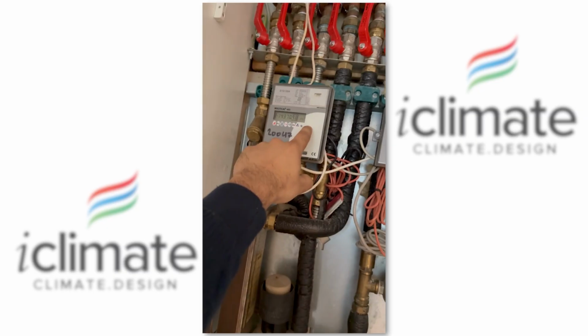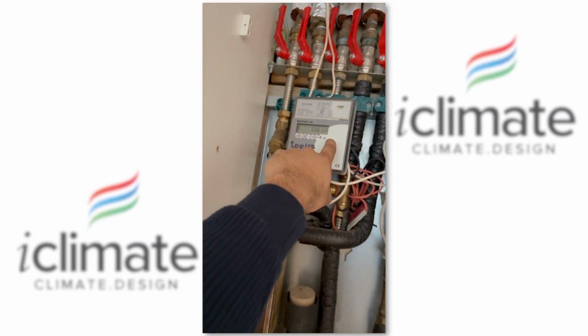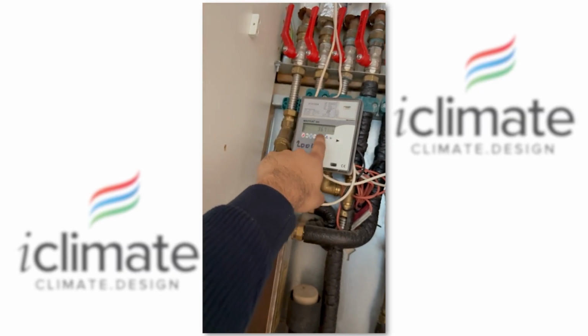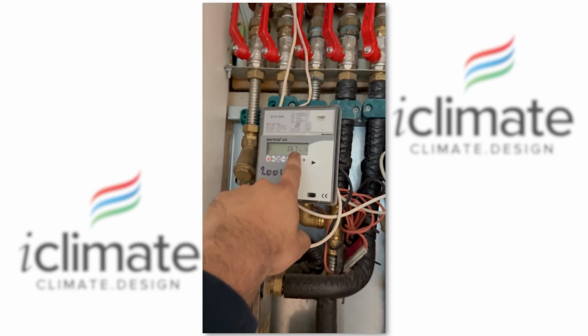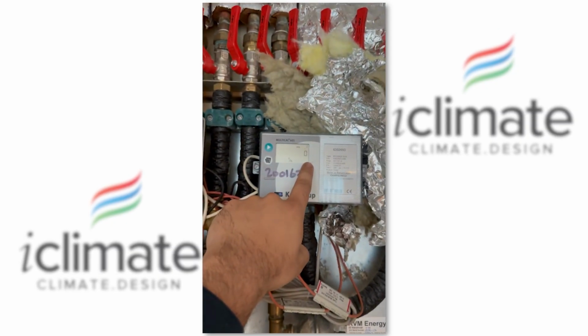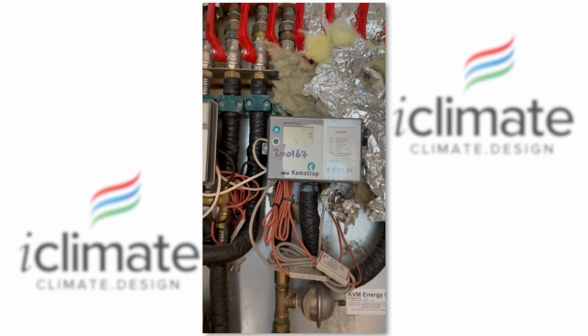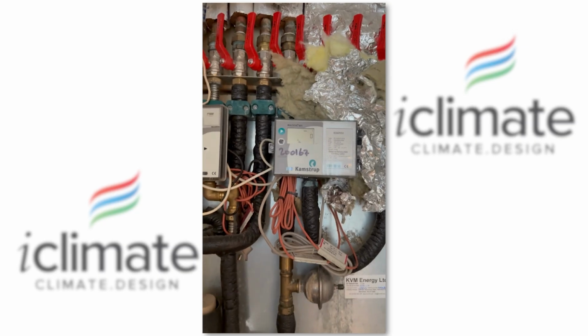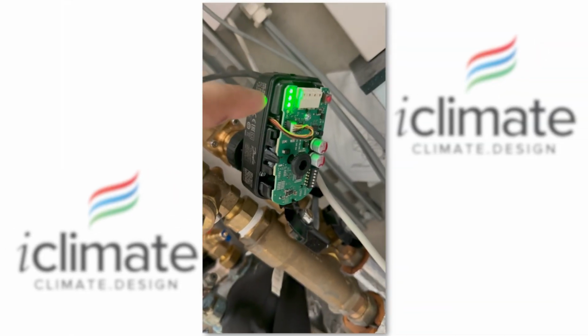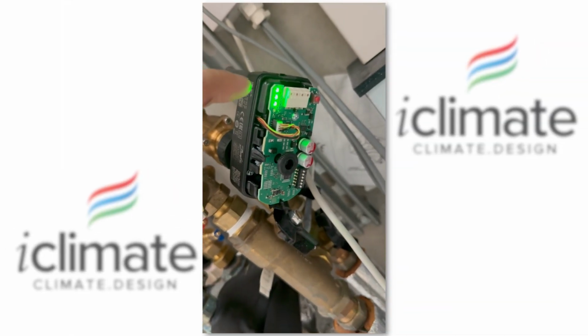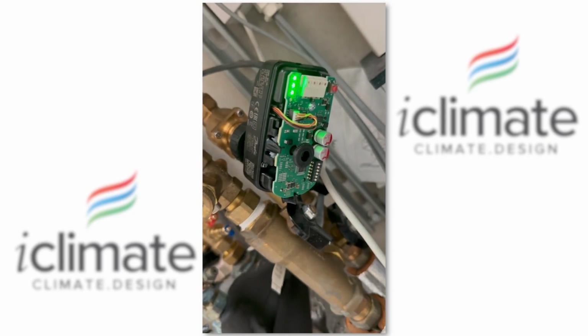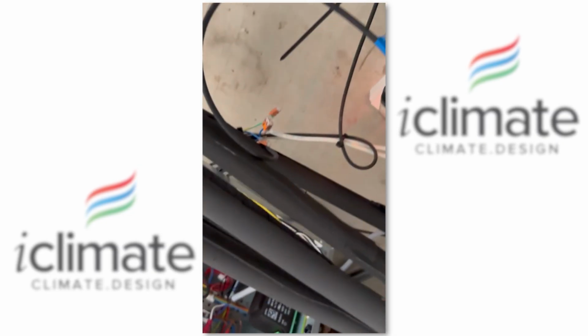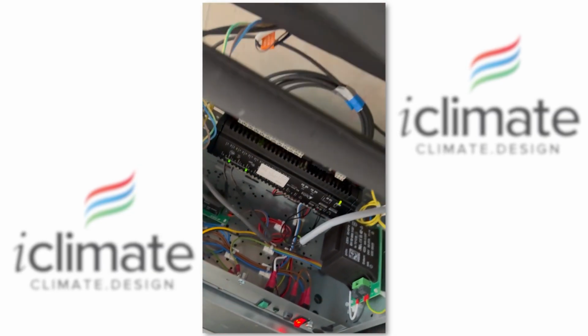And now we have flow on the hot side, and we are shut down the cooling actuator on the cooling side. So this has been configured and working properly. The 3 LEDs sitting here on the heating actuator will show that this is open a minimum of 75% under the control through the fan coil unit controller.